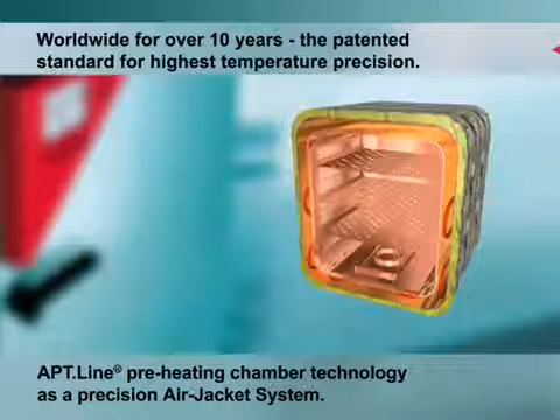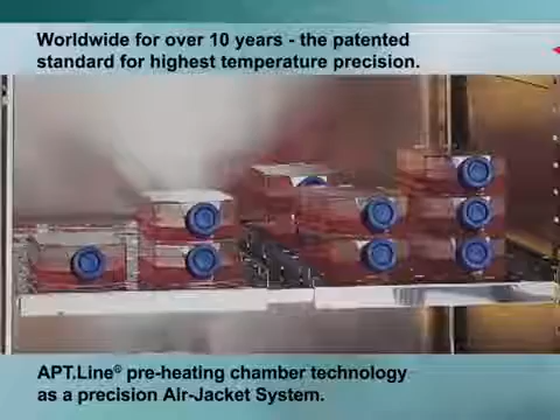And the short heating times also make it considerably more dynamic than a water jacket system. The APT.line system ensures completely homogeneous temperature distribution. The advantage for the customer is every preparation is cultured under identical conditions. Because of the superior performance and precision of the air jacket system, it does not need fans in the interior, unlike other systems. This enables us to achieve improved temperature transmission. Inadvertent transfer of contaminants is thus completely eliminated, making the CB particularly safe. The contamination risk is reduced to a minimum.